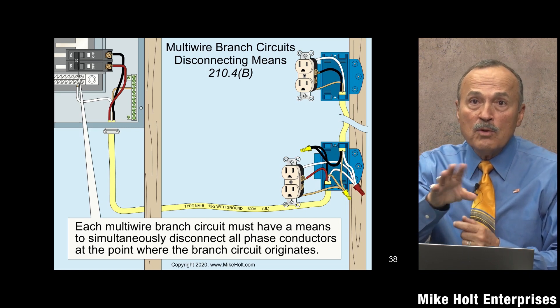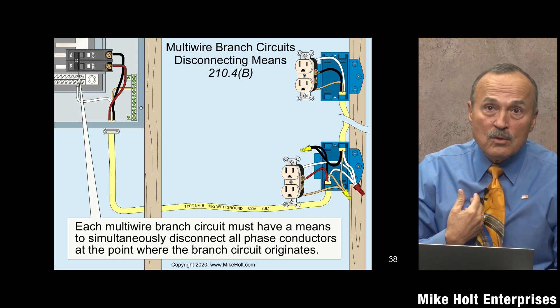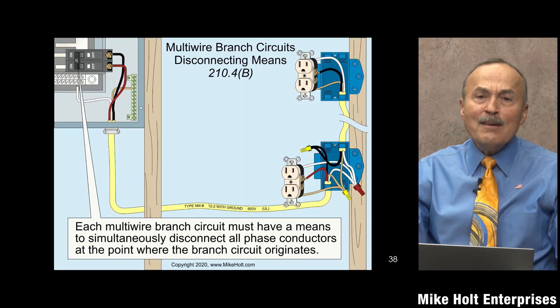Multi-wire branch circuits don't have a problem until electricians show up to work on them. For example, one electrician working at a Best Buy opened a neutral on a multi-wire branch circuit and wiped out $10,000 worth of product. The manager happened to be his buddy, so they returned the products slowly to different stores and claimed lightning damage. The key lesson: before removing a neutral from a neutral bus, put your amp meter on it first.